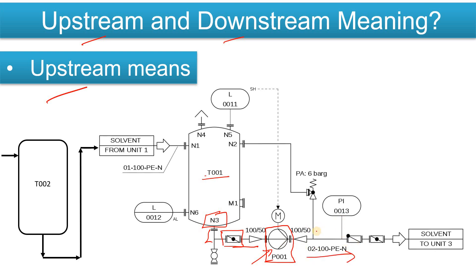In the discharge line, you will see there is one line connected to the safety valve. Whenever the discharge pressure increases, this PSV will pop up at 6 bars. Then there is a pressure gauge — a local indicator — with its tag number. Then there is your dampener, and after that again there is a butterfly valve. This is your discharge line, and I am taking this pump as a reference.